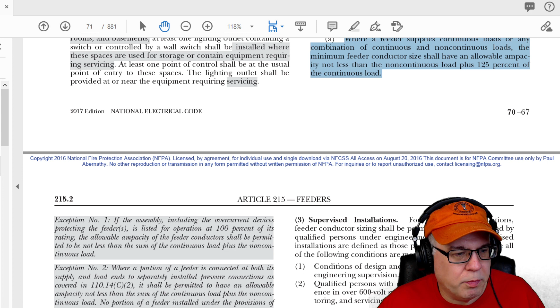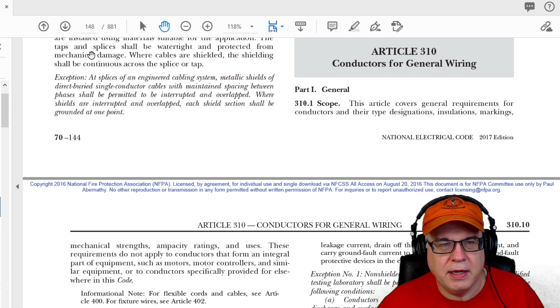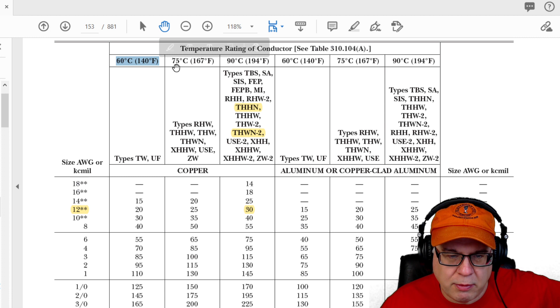All right, so the first thing I want to do, and we'll work this one out for the folks who haven't done this before, is let me close some of these because there are just too many open. We're going to go to 310.15(B)(16). Okay, and we know that NMB is a 60-degree rated conductor. So the first thing I look at is 8 gauge. I see 40 amperes. I just want to write that down.